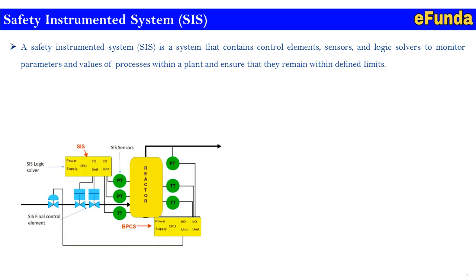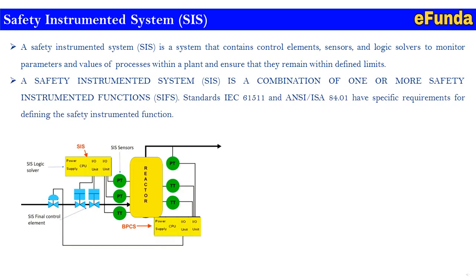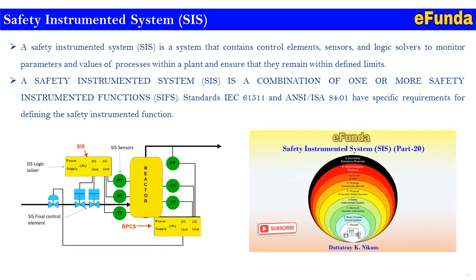This combination is used as a Safety Instrumented Function to form a Safety Instrumented Loop. An SIS is a combination of one or more Safety Instrumented Functions (SIFs) as per standard IEC 61511 and ISA S84.01, which have specific requirements for defining the SIF. We have already created a video on this topic — Safety Instrumented System Part 20 — on our channel eFunda, covering design requirements and implementation.